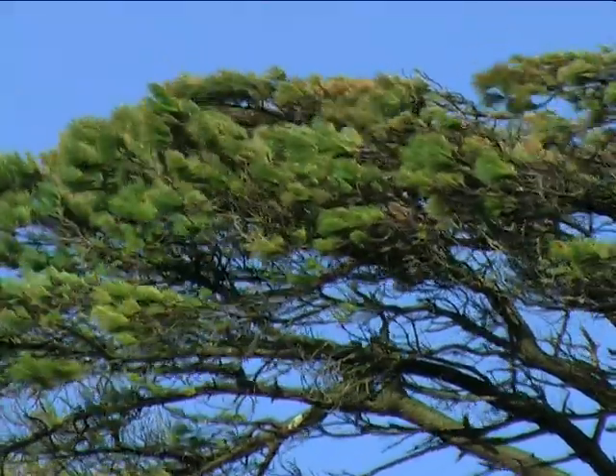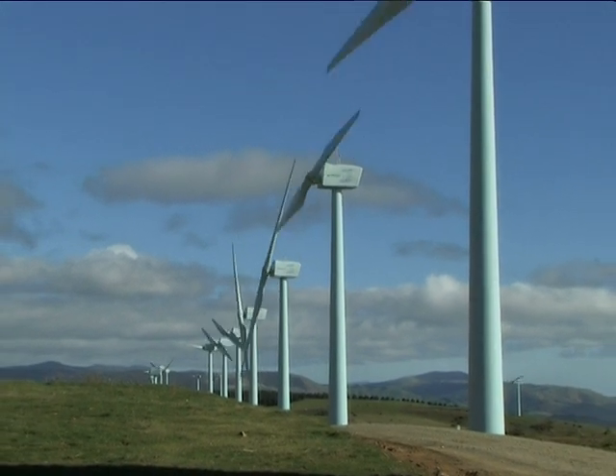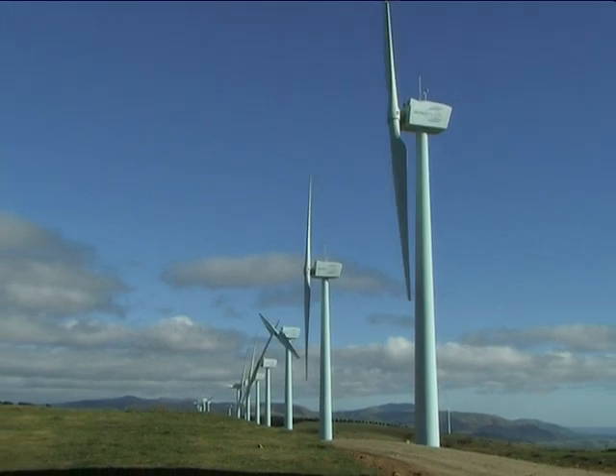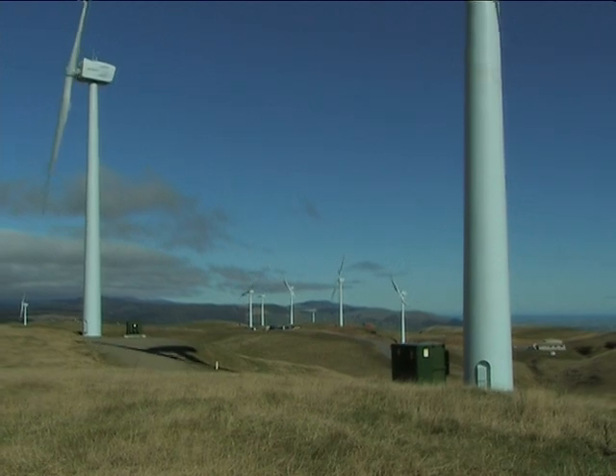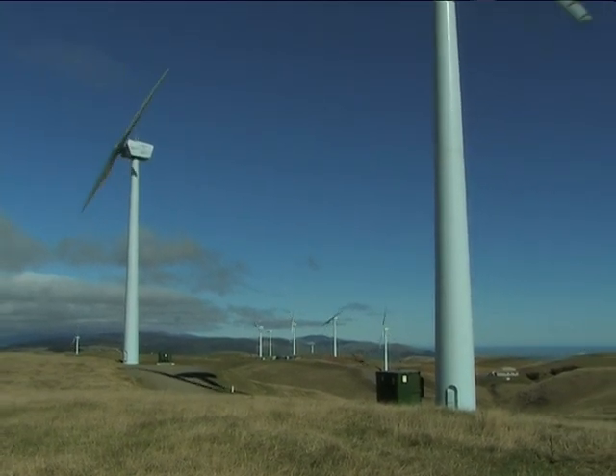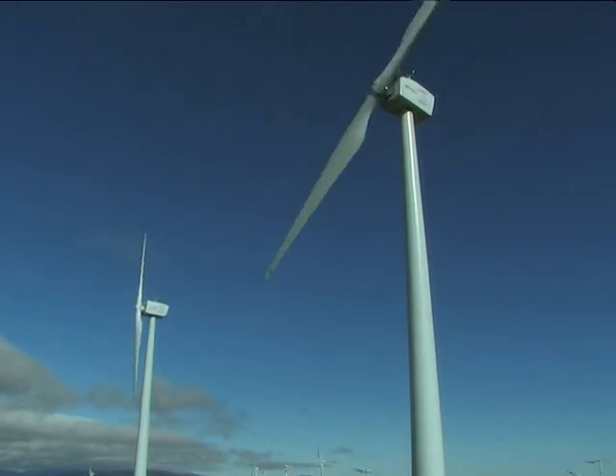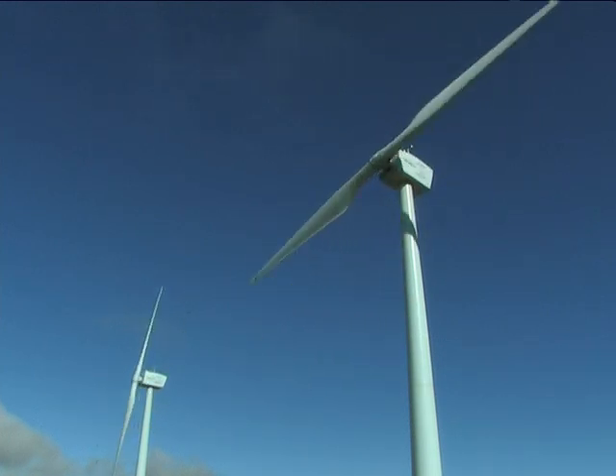Wind gusts can cause a turbine rotor to be very unevenly loaded, resulting in large bending loads on the main shaft. Teetering of a two-bladed rotor eliminates most of these bending loads, especially the most frequent ones which would otherwise affect the fatigue design. The advantage of the Windflow 500's two-bladed design is that it uses a proven method of pitch teeter coupling.